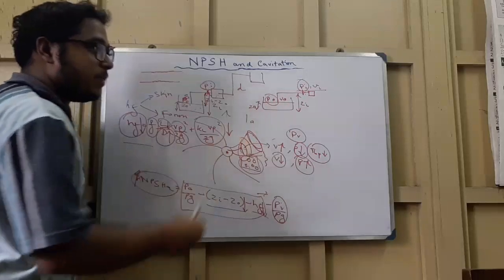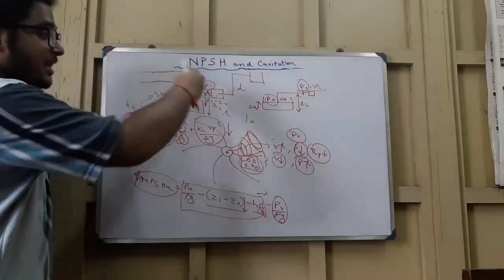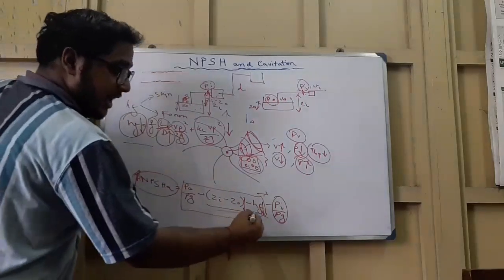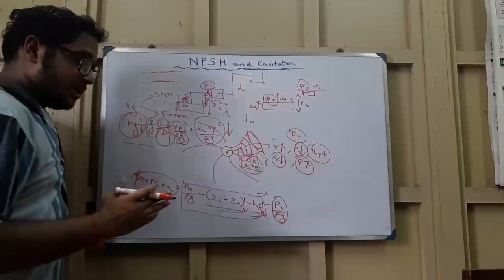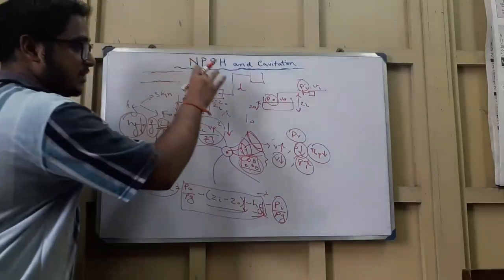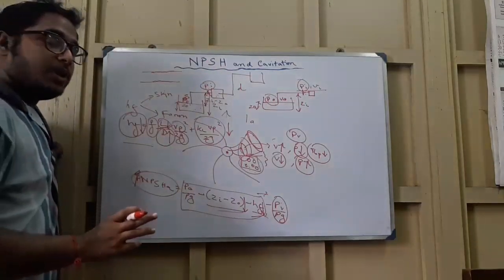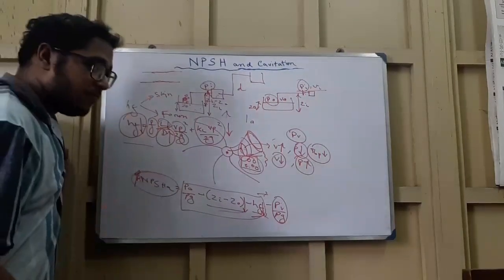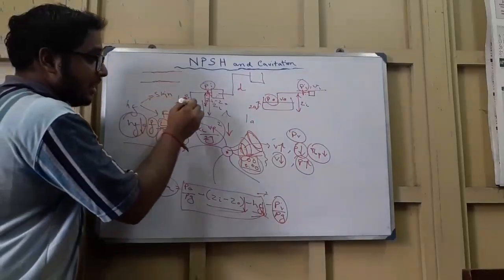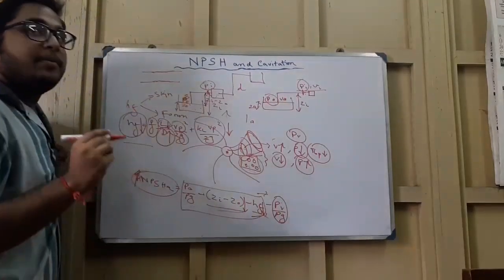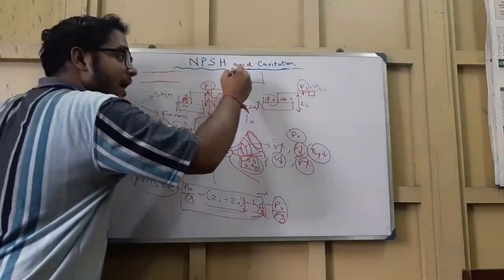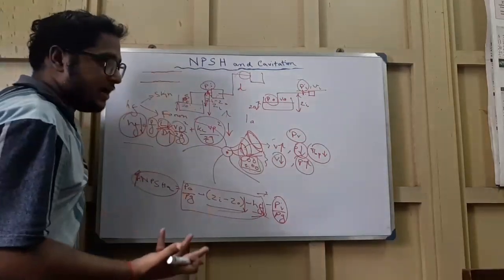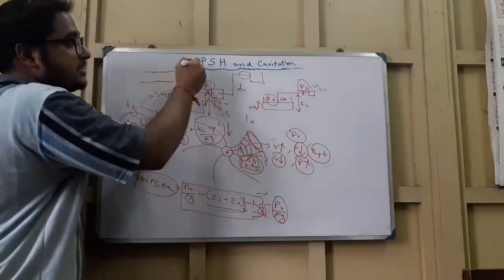So to summarize: we must reduce the losses the liquid suffers before it reaches the pump in the suction line, so that it does not lose too much energy and become vapor as it enters the pump. We keep pressure energy as high as possible by: keeping the reservoir as close to the pump as possible, keeping the minimum number of fittings, valves and bends in the suction line, and maintaining a higher diameter suction line than discharge line.